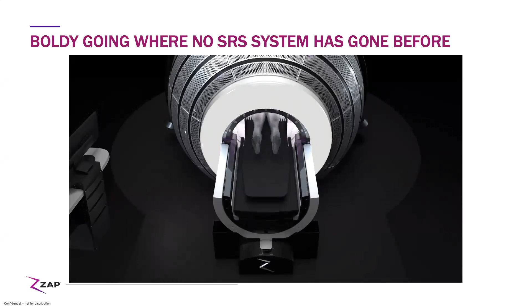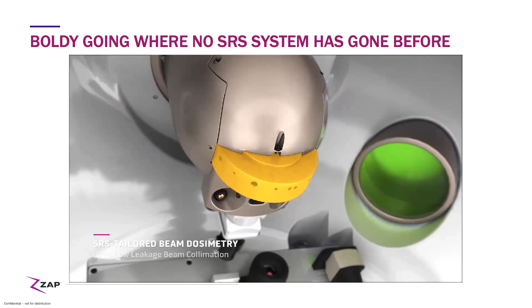There's your collimation system, 800 pounds of tungsten, which blocks almost all the primary scatter. And what you're left with is a finely emitted beam of radiation coming through one of these cylindrical collimation systems. It's literally in a second or two that we can change apertures from 4 millimeters to 2.5 centimeters. That gives you far more flexibility than any pre-existing radiosurgical system with cylindrical collimation.